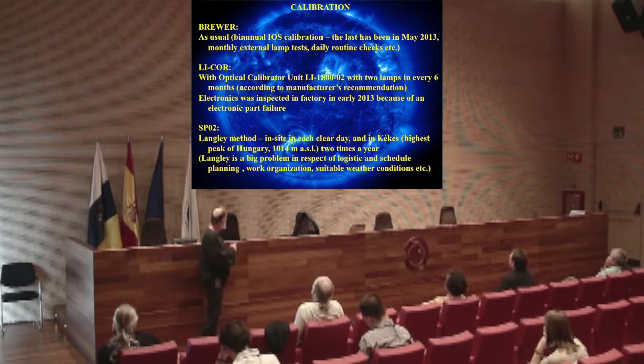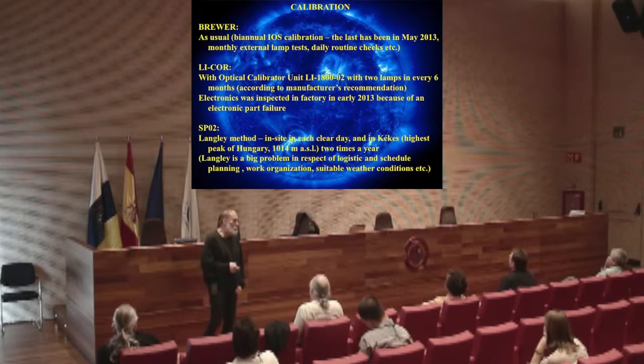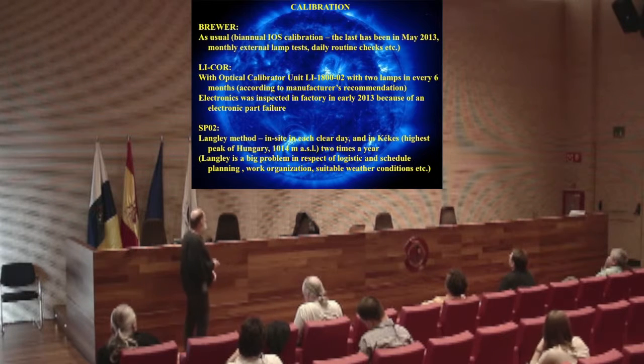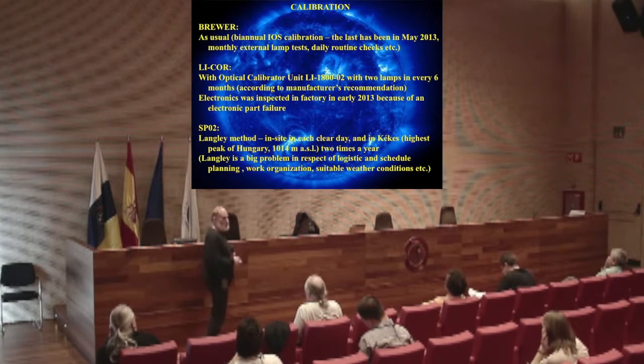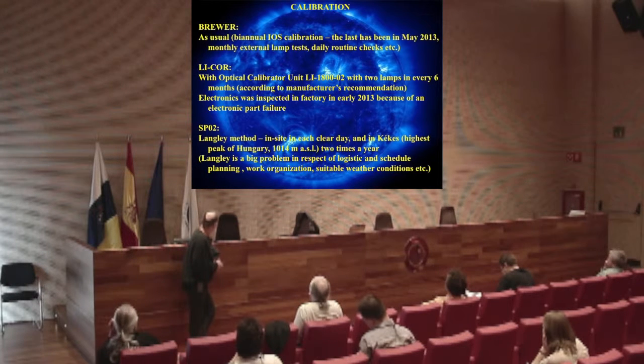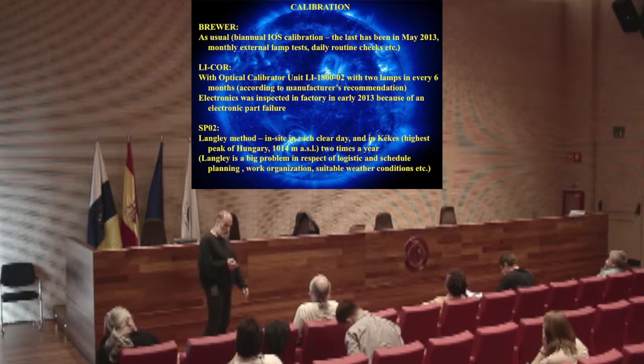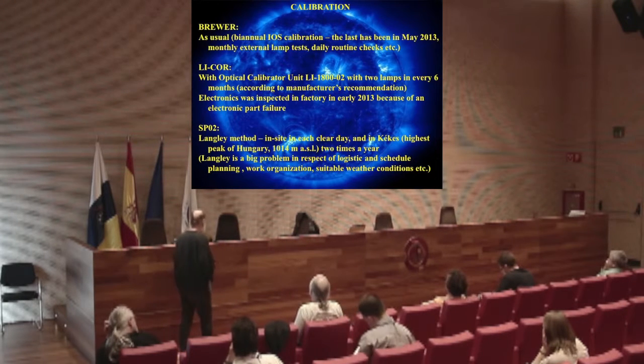LICOR is calibrated. We have a manufacturer optical calibrator unit for the LICOR, a lamp. So it is calibrated every 6 months. It is the recommendation from the manufacturer. And the electronics had a problem last year, so it was repaired in the factory.